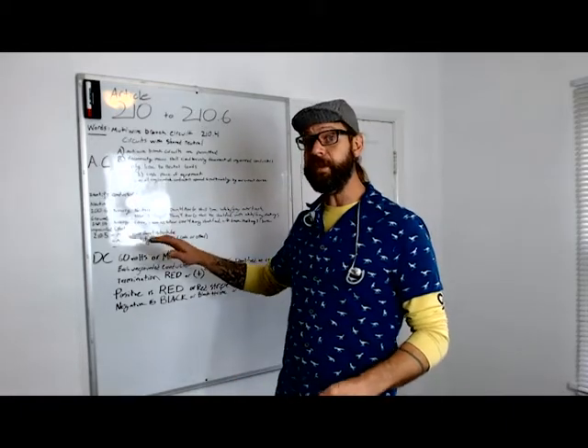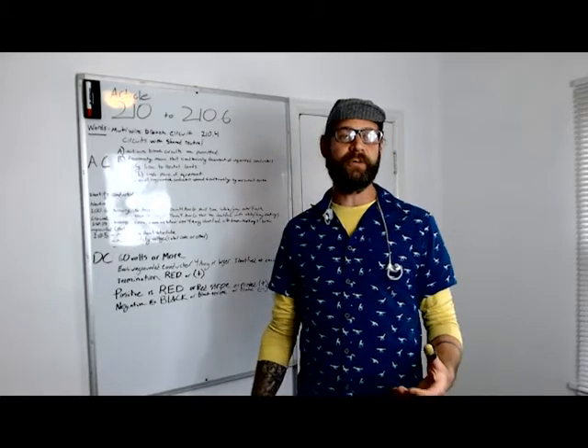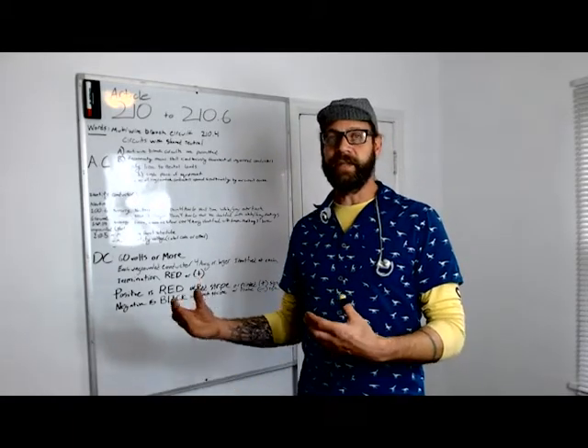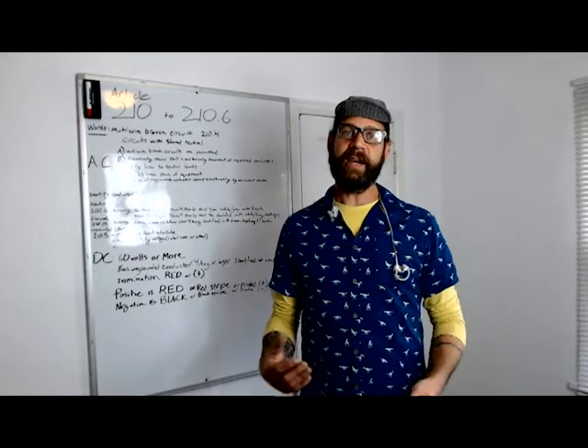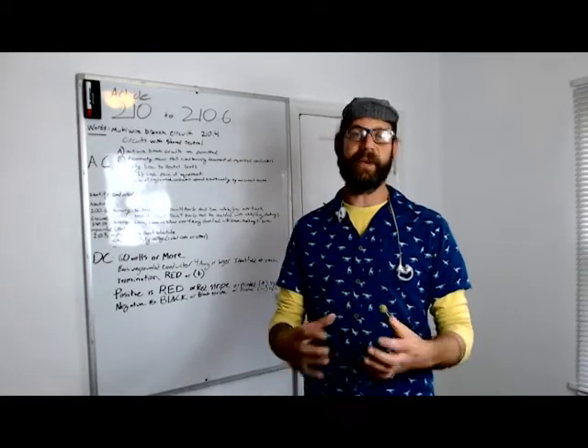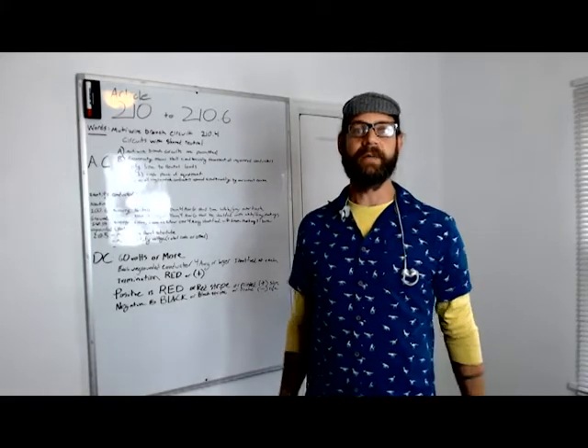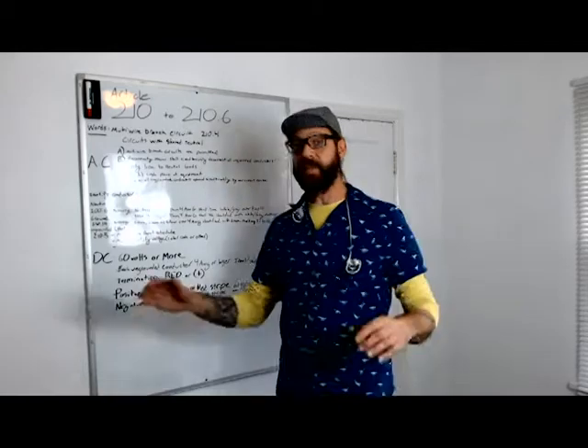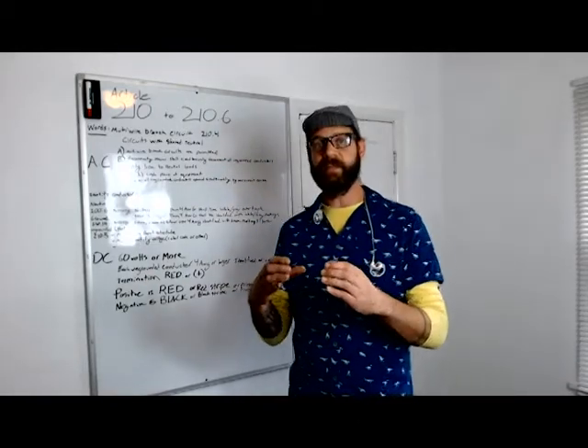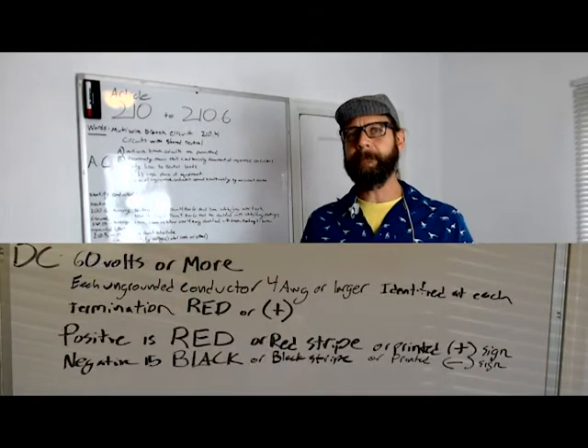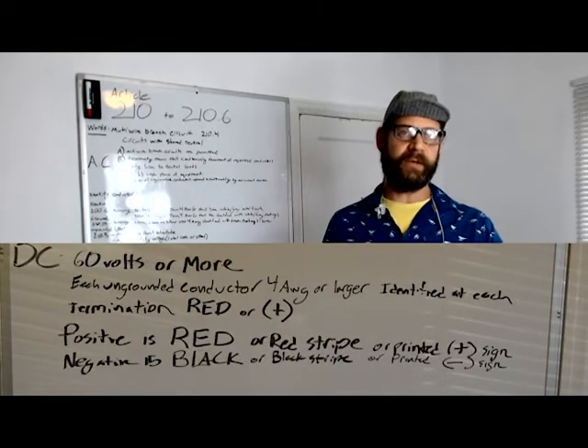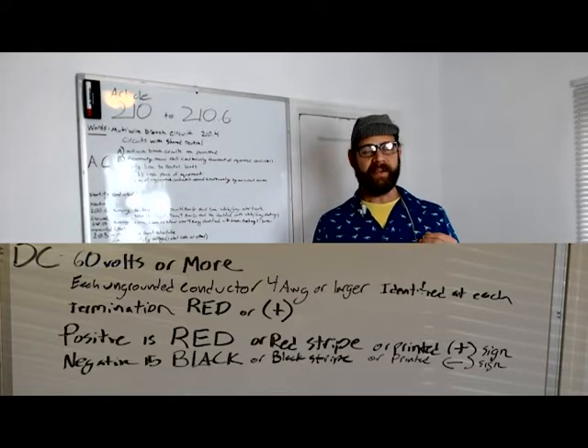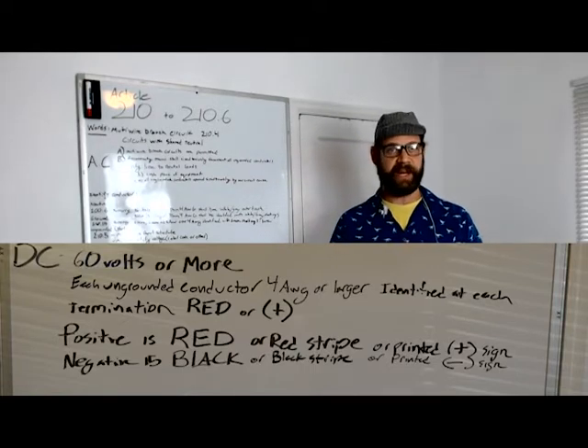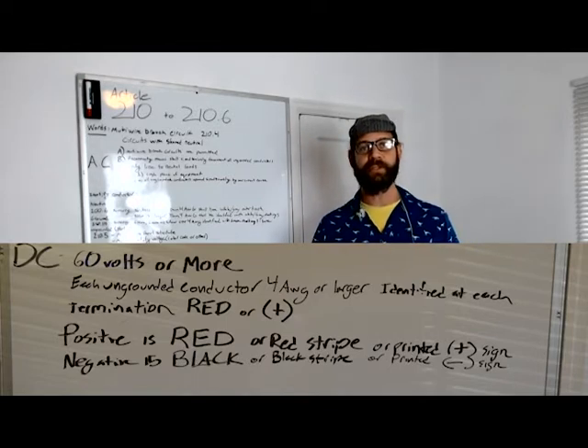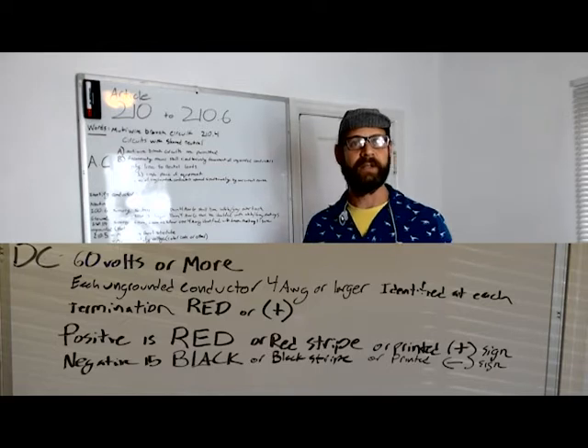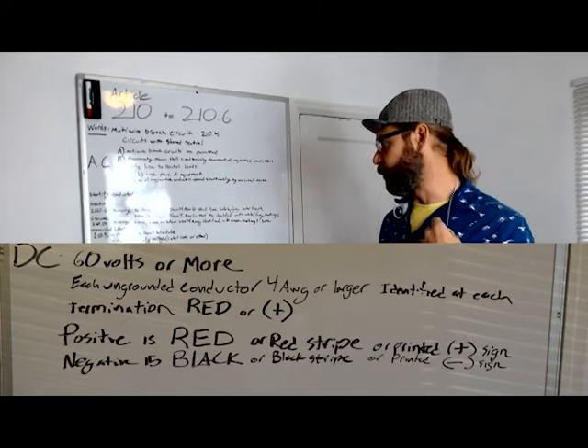It is permissible by code to use any combination of labeling or color coding that is not industry standard, as long as that is put onto the panel and available and people generally know what it means. There you go. So this section also goes through DC circuits. One of the most important things to know about this code section is we're dealing with DC circuits of 60 volts or more. If a DC circuit is 60 volts or less, it doesn't apply to this code section at all, and you need to look up a low voltage code section or freedom, do whatever you want. But this is DC 60 volts or more.